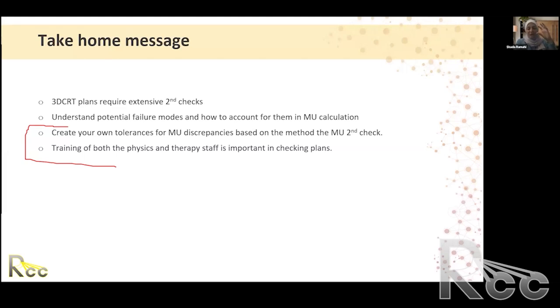The equation, so remember your K, your 1 centigray per monitor unit. You want to make sure that you know exactly how you get the 1 centigray per monitor unit, and then you do whatever is needed to correct back to it. The options you have are PDD, TMR, or TPR, tissue maximum ratio or tissue phantom ratio, or of course the percentage depth dose. And then the field size correction is the same. It's dose for this field divided by the dose to that field. But the measurement is at your reference geometry. So if your LINAC is calibrated at Dmax, then you put the ion chamber at Dmax and you start changing the field size and you take the ratio. If your LINAC is calibrated at depth, then you put the chamber at depth, you change the field size, and basically you're trying to capture the differences in the output at the reference geometry for different scenarios.